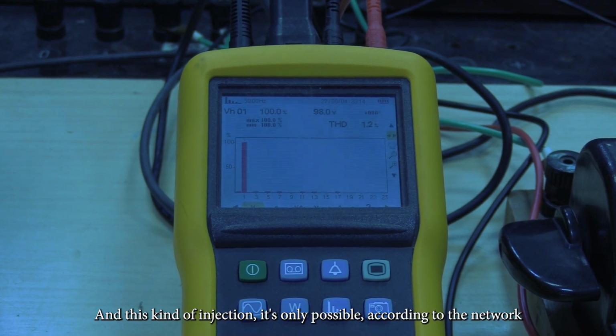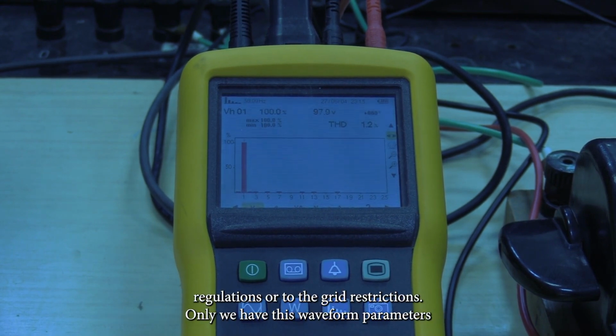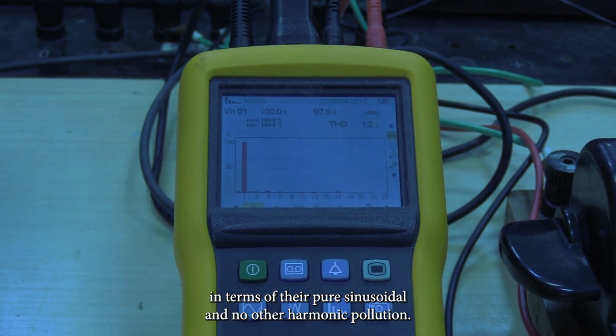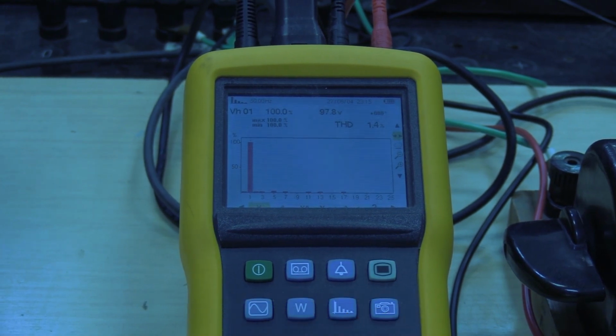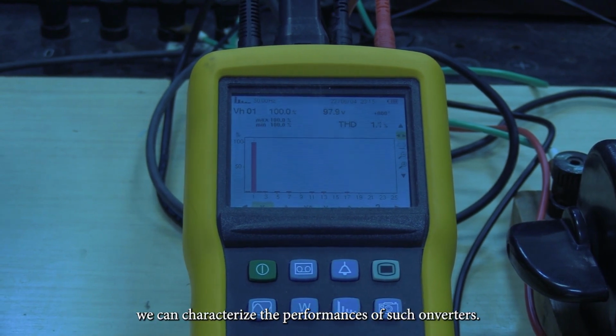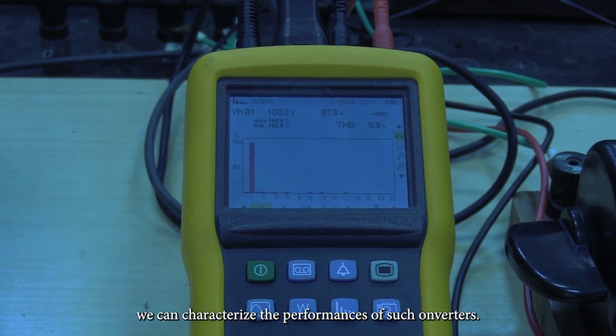And this kind of injection is only possible according to the network regulation or the grid restrictions, only if we have these waveform parameters in terms of pure sinusoidal shape and no other harmonic pollution. That's why it's important to measure, and in this way we can characterize and measure the performance of such inverters.